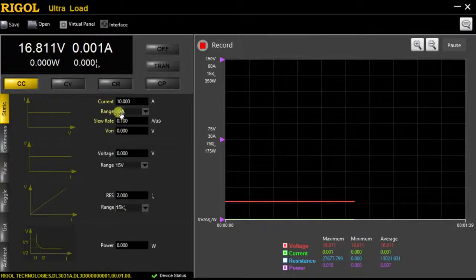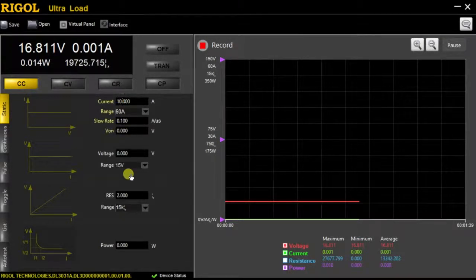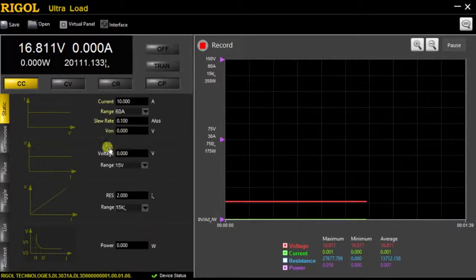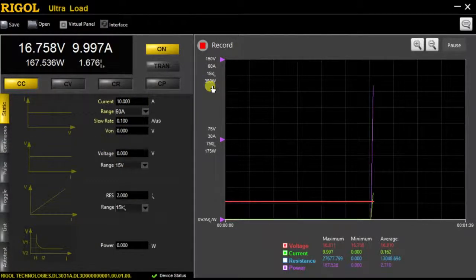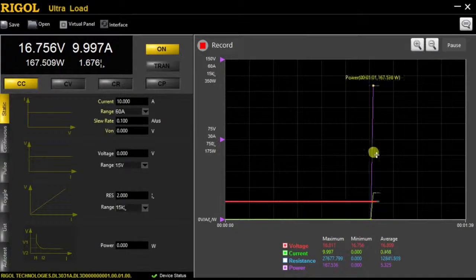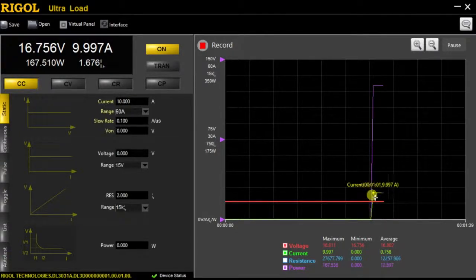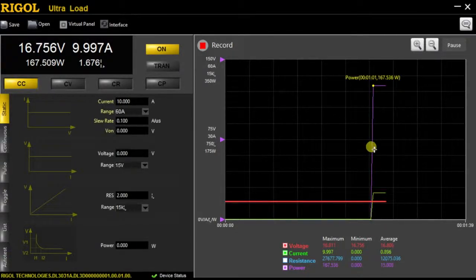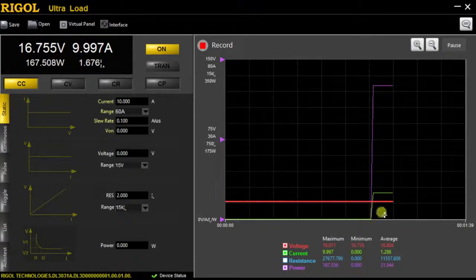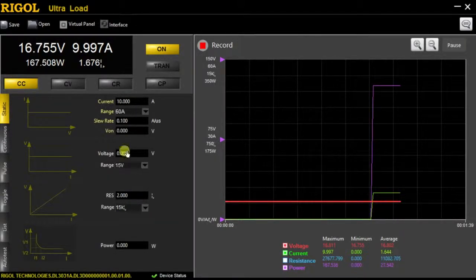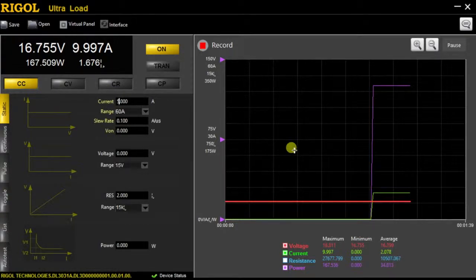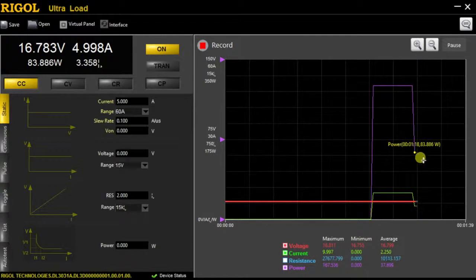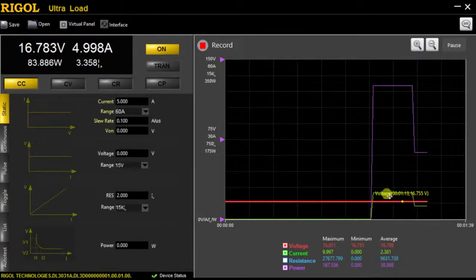So just to demonstrate it, I'm actually going to set the current for 10 amps here, and then I'm just going to turn on the load itself. And we're going to see a spike up in both power and the current level in green, and the power in purple. With the current level starting to be drawn, our voltage will remain constant. We can also change this level by setting it to five, and then we'll see it drop down, both power level and current level, and our voltage will also remain constant.